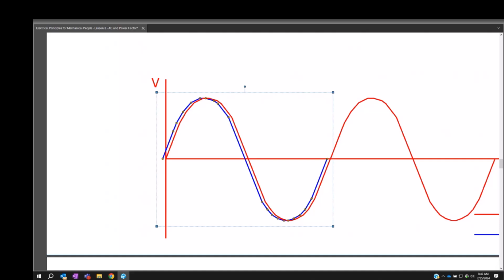But since we're keeping everything high level, just understand most of the time you want a 0.95 to 0.98 power factor. That's normally how we tune the cap banks, stepping them in - this many caps, then this many more, based on power factor and what motor's operating.